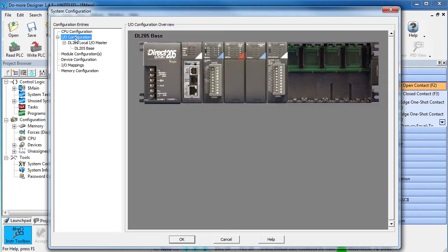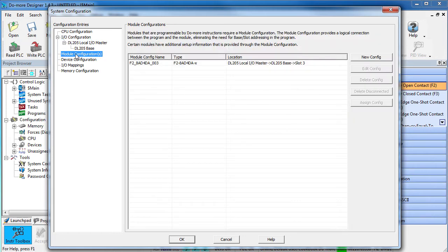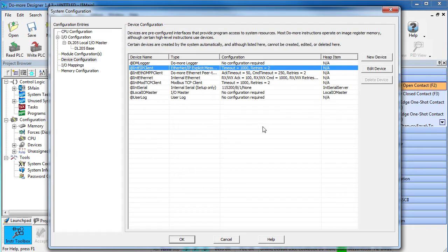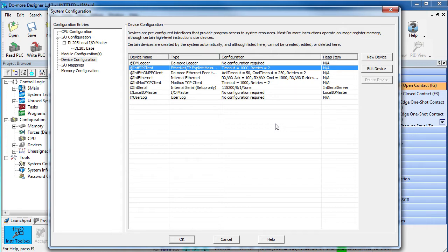We're not adding any I/O to the Do-more so there's nothing to do here. And we're only using the built-in Ethernet port and we're not adding any new modules to the PLC so there's nothing to do here. Under Device Configuration, we could use the built-in Ethernet IP device to talk to the Matrix 210, but it's always better to create a new Do-more device for each piece of hardware you want to talk to via Ethernet IP. That way no Do-more device has to manage multiple TCP IP connections, which would slow down your code.